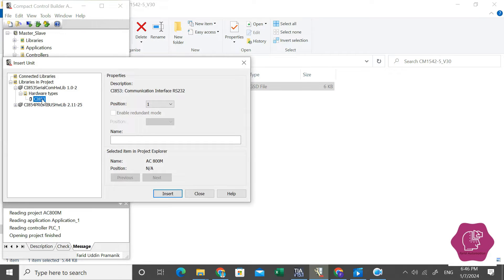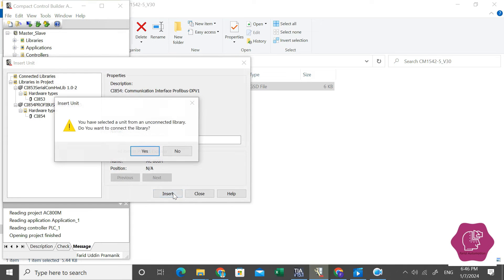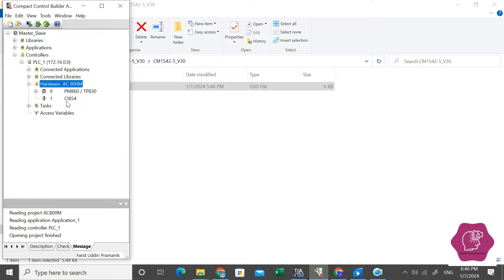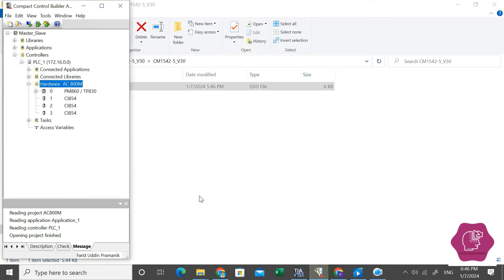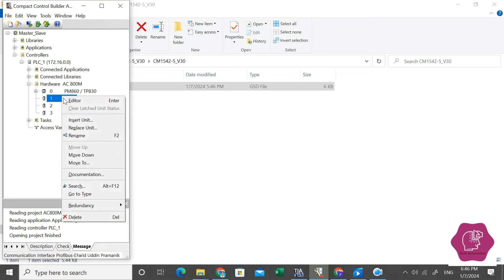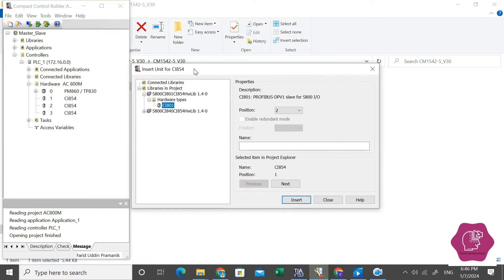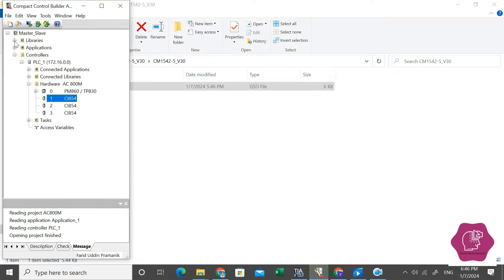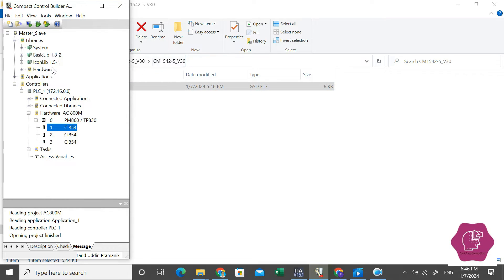CI853 is a Modbus master module and we want to add the Profibus hardware, so we need CI854. This is CI854 — you can add more, like one, two, three. Now I will add the GSD file first. I have to add the CM1542 module, but here it's not found in the library. So you have to add that library and add that hardware GSD file in the hardware library.